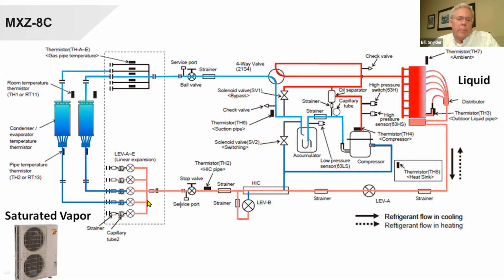We go into the branch box, where it's split up. In this case, we've got a 5-head branch box. These are 5 LEVs, which is what's pictured here. These are cap tubes. And then we go out to the indoor coil. We've got an entering coil temperature thermistor, a room return air temperature thermistor, and a leaving coil temperature thermistor that's actually in the branch box, coming back in through the service port ball valve and through a strainer. We're looking at another thermistor. Then we go through this hybrid accumulator into the suction port, and through here we're taking some gas and changing the temperature state and feeding some refrigerant back into the compressor to keep the compressor cool and to get as much heat as we can out of the system.